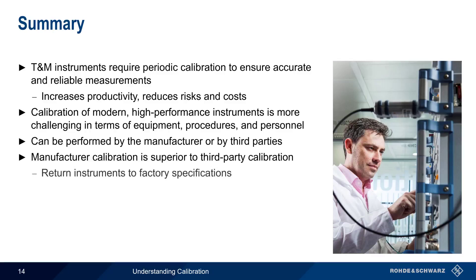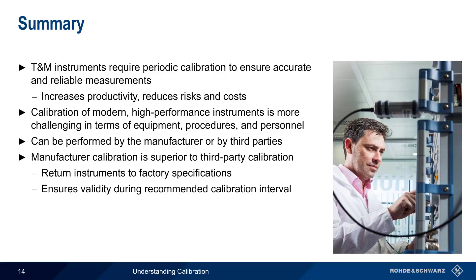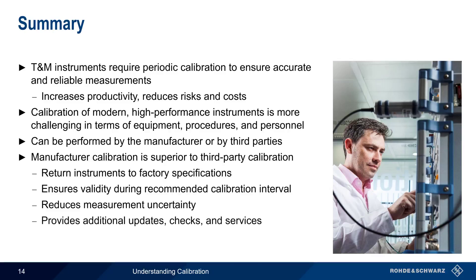A manufacturer calibration returns the instrument to factory specifications, with alignments performed even when values are within the nominally acceptable range. This ensures that the instrument remains in-cal and provides valid results during the recommended calibration interval. The higher quality and more comprehensive calibration procedures used by the manufacturer reduce measurement uncertainty and provide greater confidence in measured results. Manufacturers also typically provide many additional checks and services, such as firmware updates and preventative maintenance, during the calibration process.